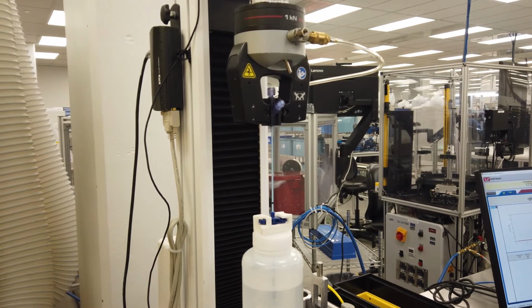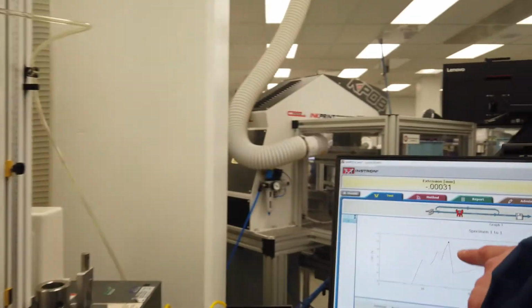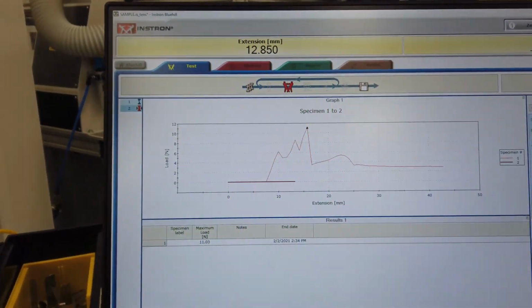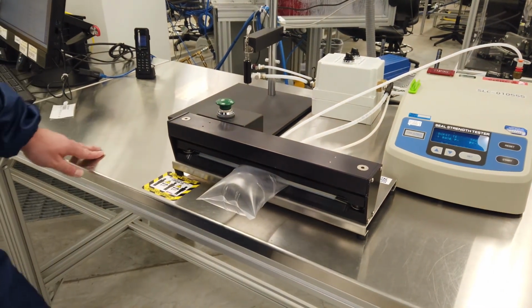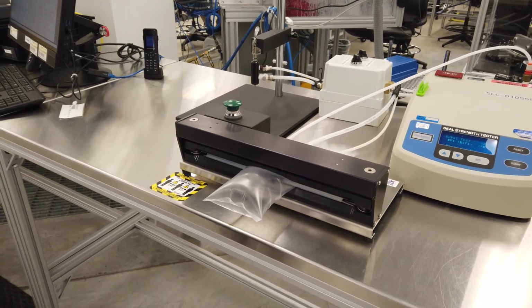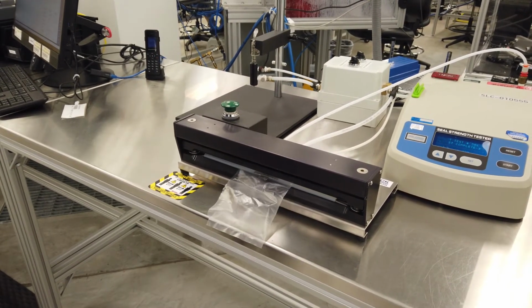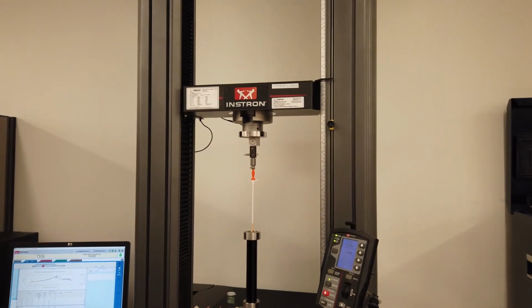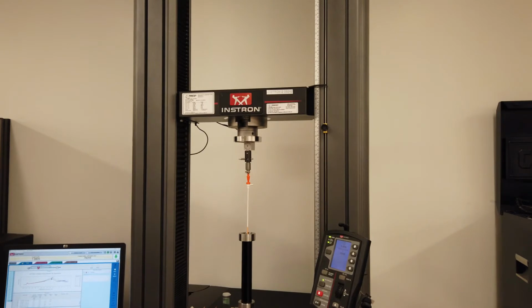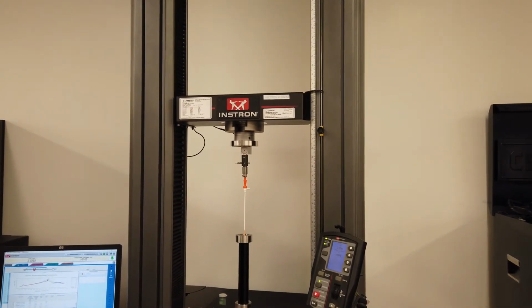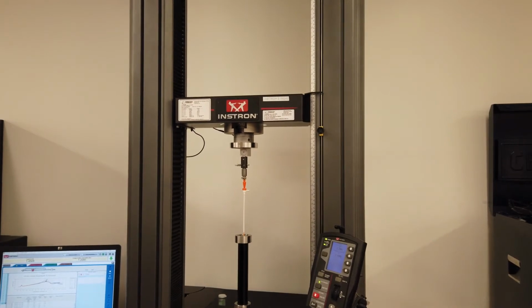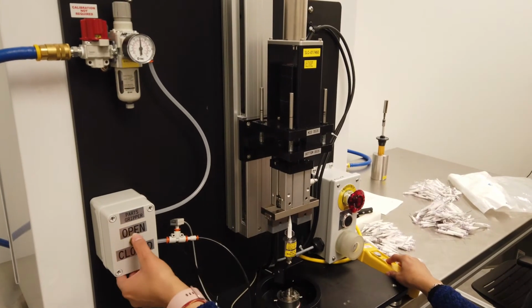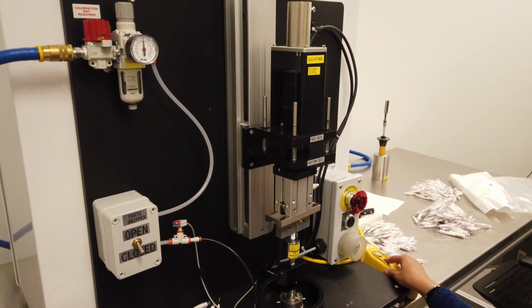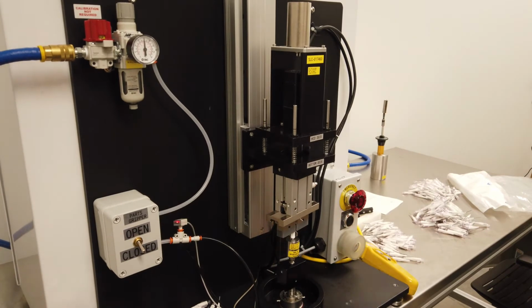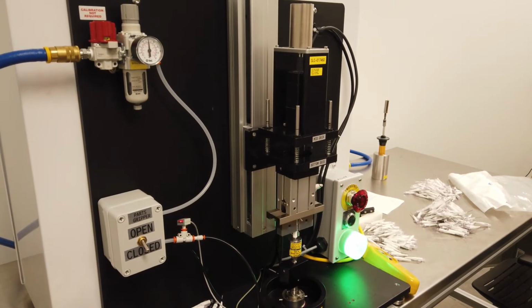In this test, the force is being measured to withdraw a catheter through an introducer that is submerged in fluid. This next test, we are testing the pressure a bag and a seal made on the bag can hold. You can see that the bag material fails, not the seal. This equipment is measuring the force of inserting a sheath in a dilator assembly. This equipment is measuring the torque to tighten a luer fitting and to untighten it.